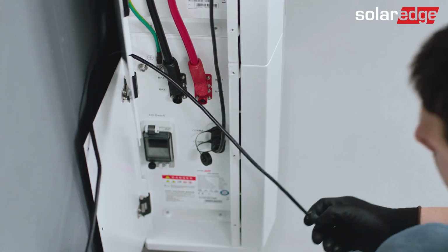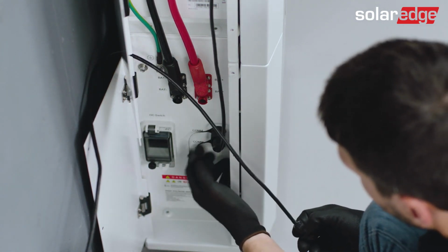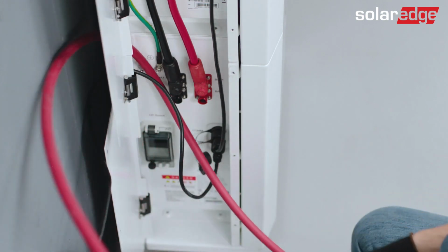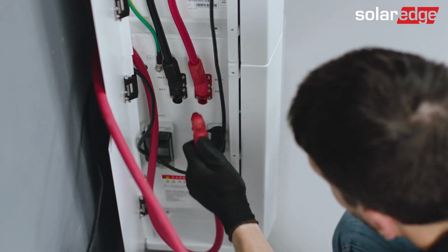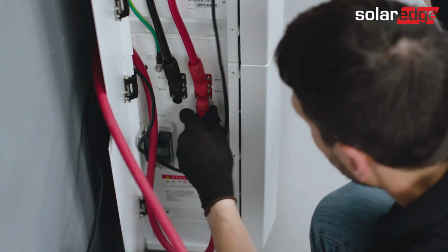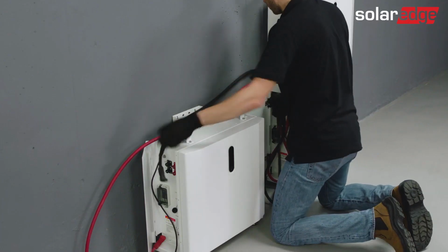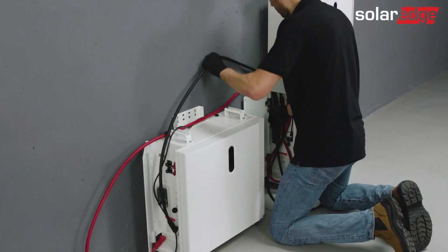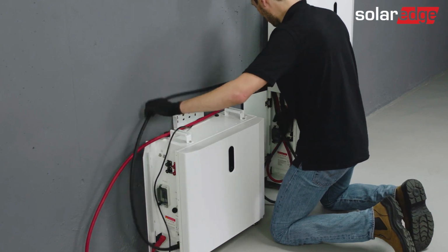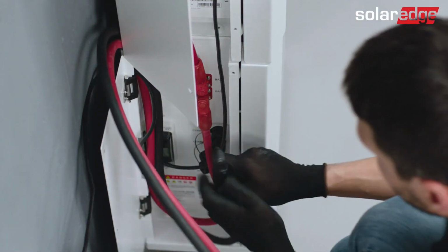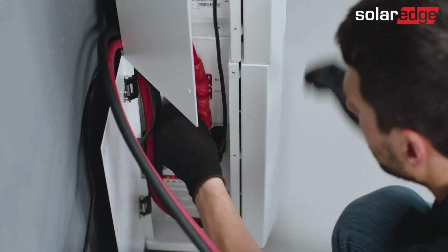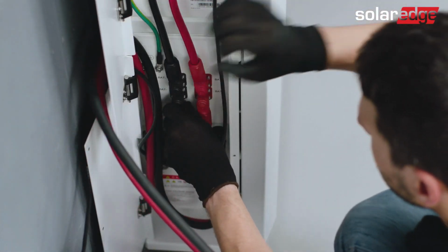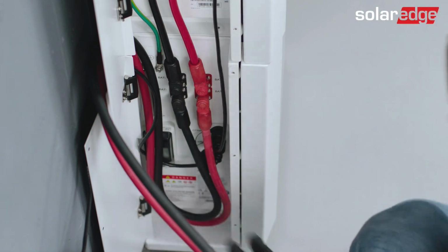First, connect the communication and ground cables between the towers. Please pay attention that the cables shouldn't be lying on the ground. Wire the cable above the battery left cover, and only then connect them to the right connector. Then, connect the DC red and black cables between the towers. Choose a bottom connector with a matching color in each battery. Similarly, first wire the cable above the left cover, avoiding laying it on the ground.